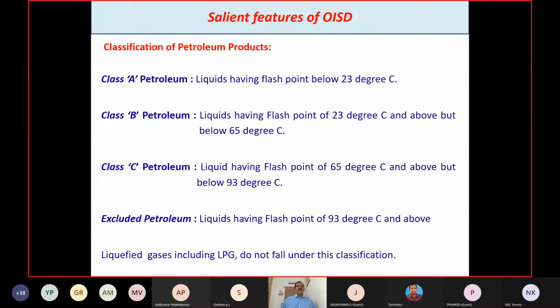Here, this is a very basic thing that everybody should know. That's what I wanted to inform you. The classification of fire: the petroleum products are also classified based on the flash point. So here, liquids having flash point below 23 degrees centigrade are categorized as class A petroleum, and liquids having flash point of 23 degrees C and above but below 65 degrees centigrade are categorized as class B petroleum, and liquids having flash point of 65 degrees centigrade and above but below 93 degrees centigrade are categorized as class C petroleum.